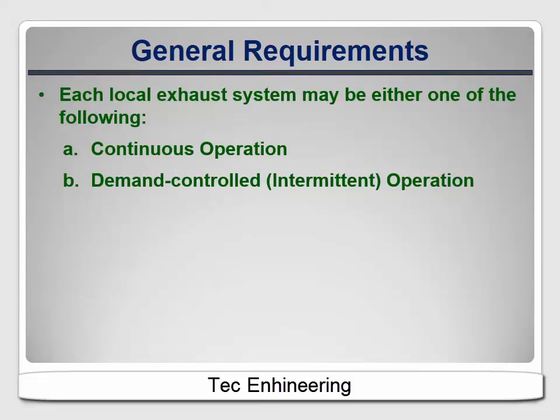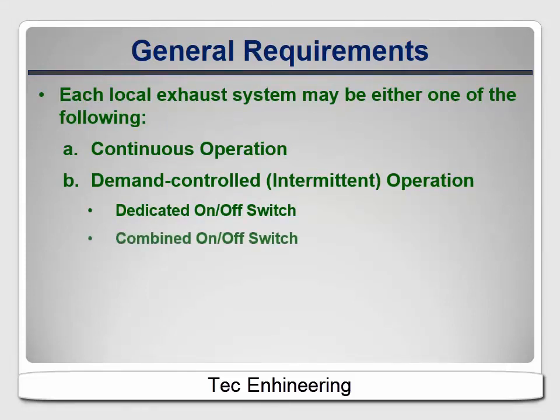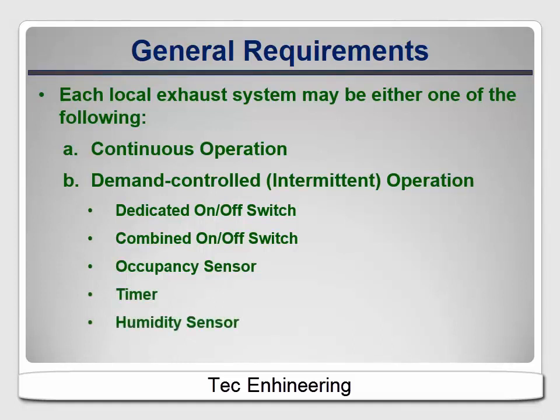Demand controlled systems are much more common and are often also called intermittent systems. They can be activated by a variety of means: a dedicated on-off switch like a wall switch for a bath fan or an integrated switch for a range hood, or a combined switch where turning on the light also turns on the fan. Other acceptable options include occupancy sensors, timers, and humidity sensors for bath fans.